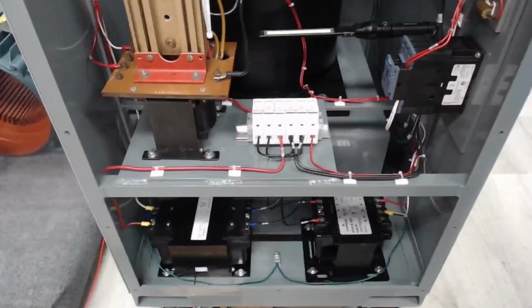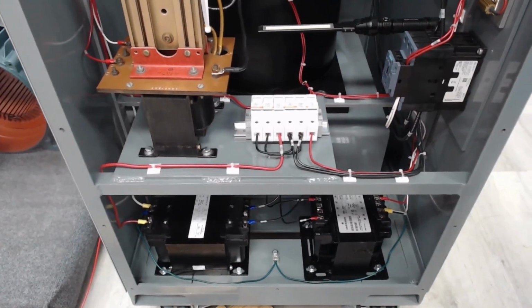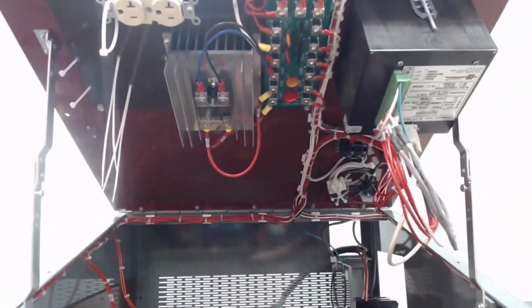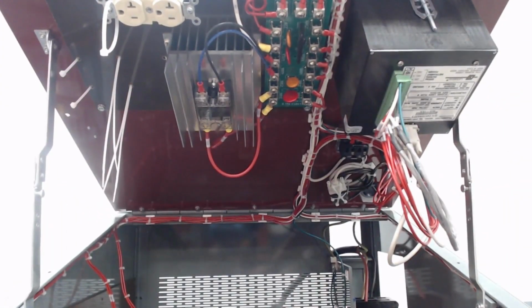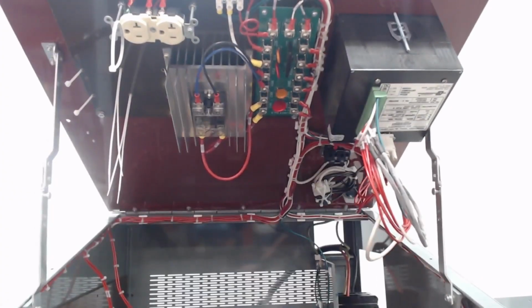You should check these two transformers down below. So those two black transformers, your incoming voltage should be whatever your unit is set up as at your facility, but the output needs to be 120. 120 volts AC, doesn't matter what's going in, 120 volts AC should be coming out. If it's deviating too far, more than your 10% variance, then you've got an issue and you need to resolve that first before you move forward with anything.